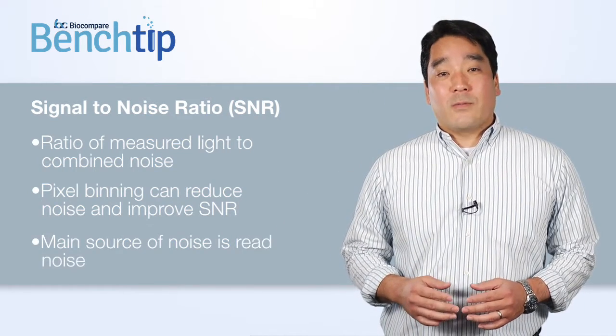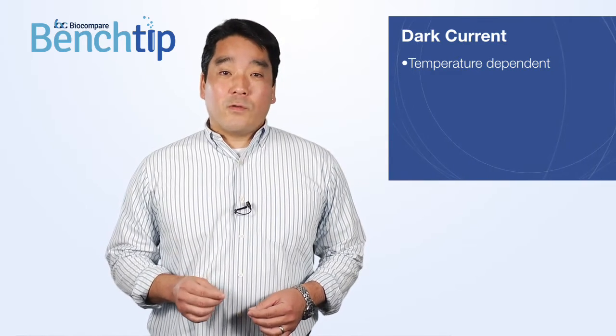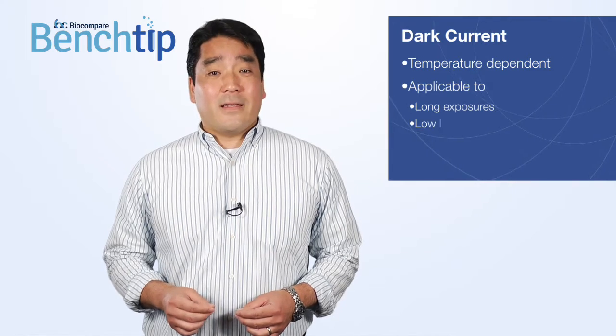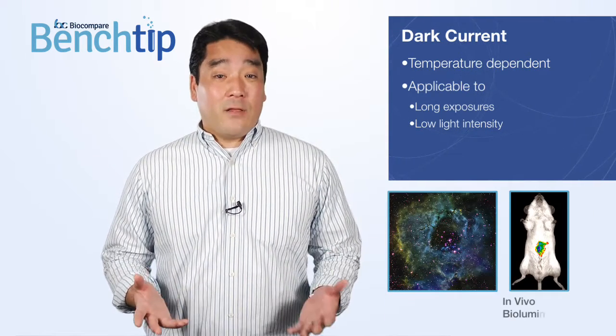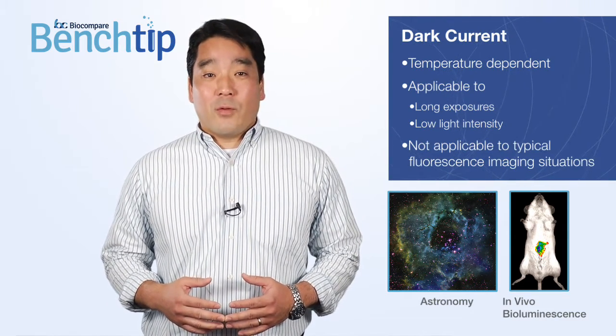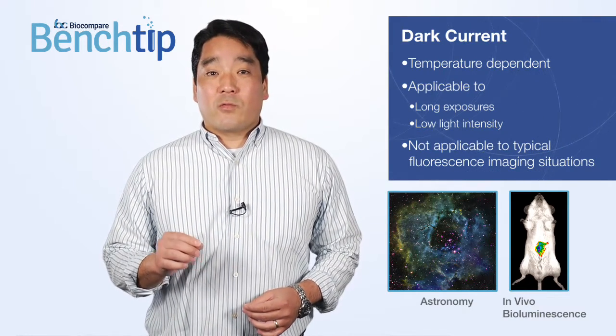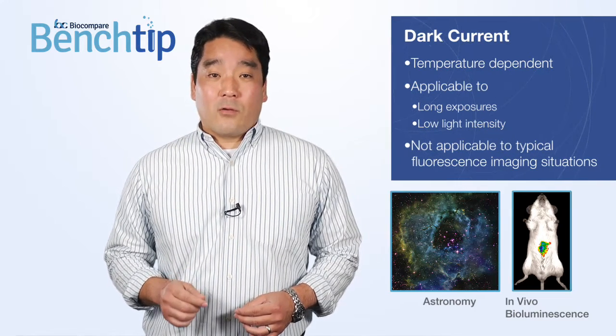The main source of noise in fluorescence microscopy with shorter exposures is read noise, which is typically much higher than dark current noise. Dark current, another source of noise, does depend on the temperature of the sensor. Cooling the camera reduces dark current noise and should be considered for situations requiring long exposures, or if light intensity will be extremely low, such as in vivo bioluminescence or astronomy. In general, dark current will not have a major impact on typical fluorescence imaging situations. So unless you are imaging under conditions requiring long exposures or low light intensity, dark current will have minimal impact on your imaging.